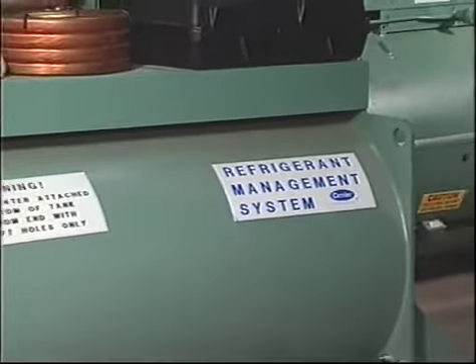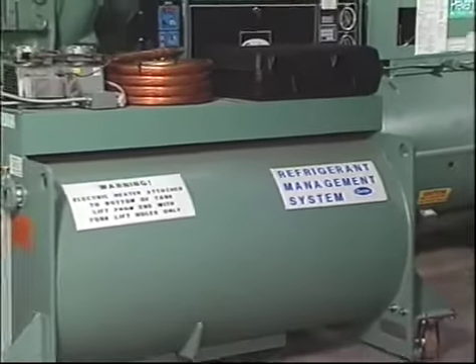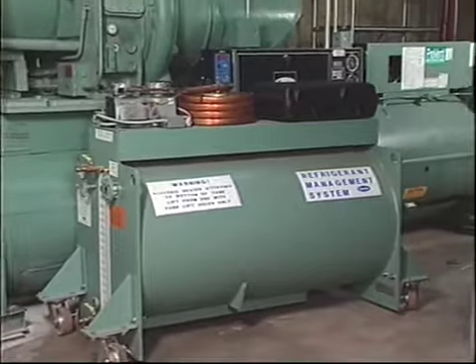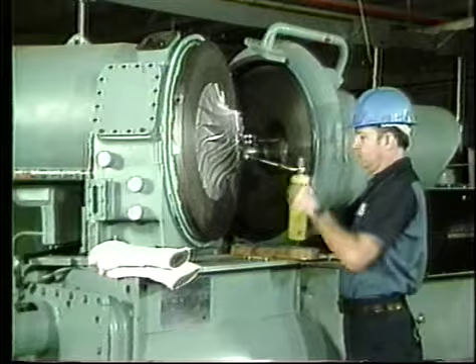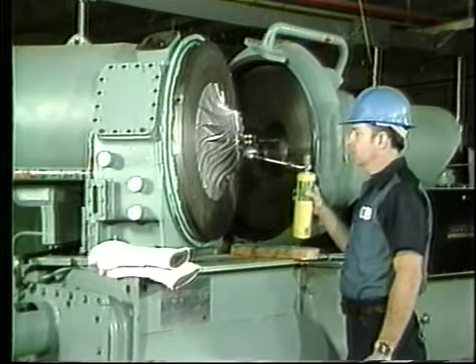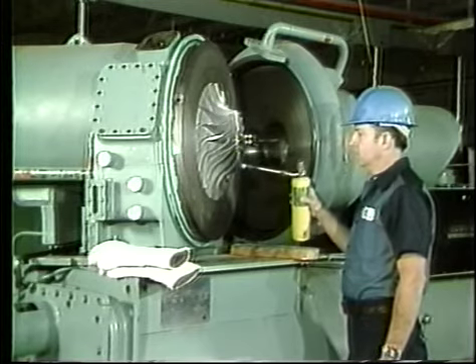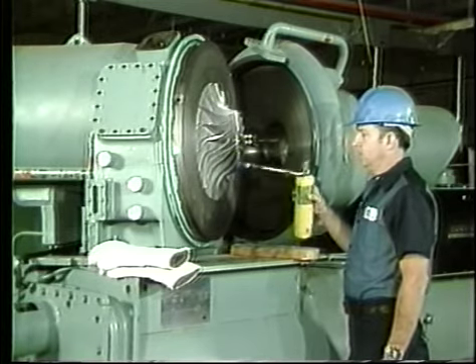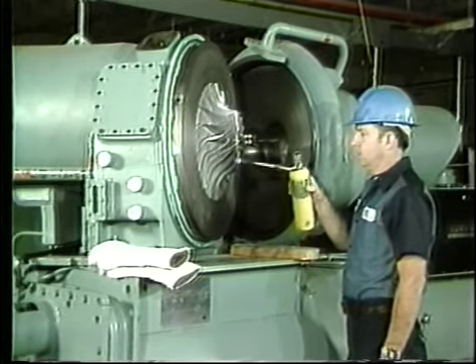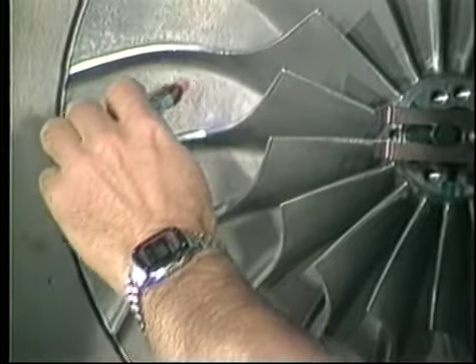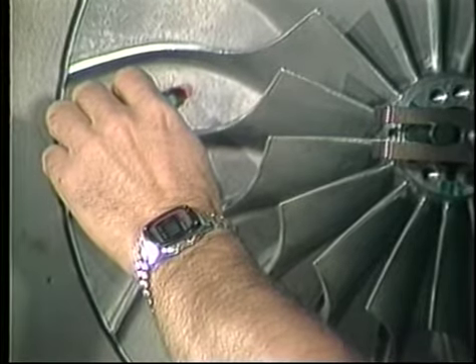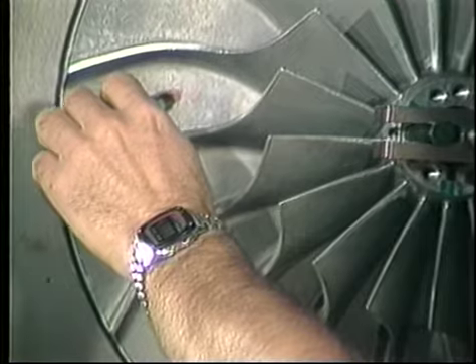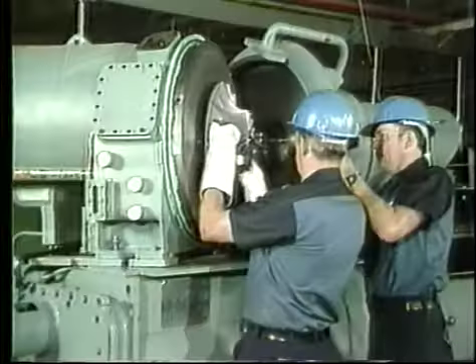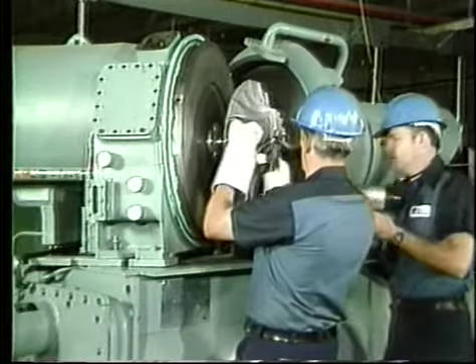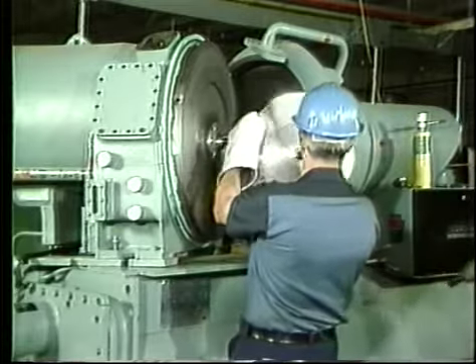Containment means taking all reasonable steps to ensure that refrigerant is not lost to the atmosphere. Conversion of a low-pressure chiller to a different refrigerant can cost almost as much as a new chiller, so it may not be a good choice. If the machine is relatively old, replacement may be the best approach. If it's relatively new and is in good condition, containment will probably be the most economical approach.